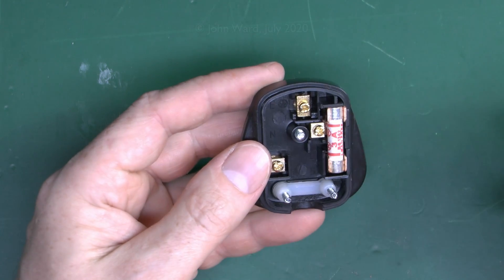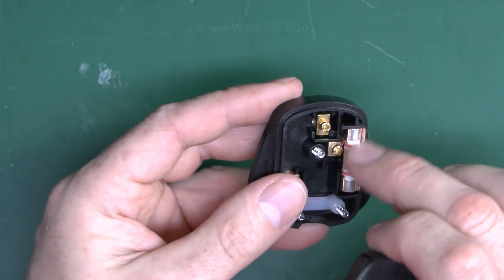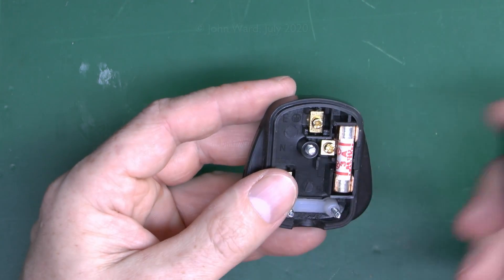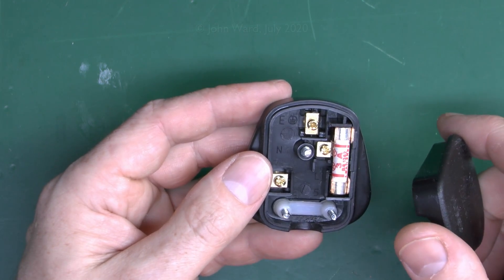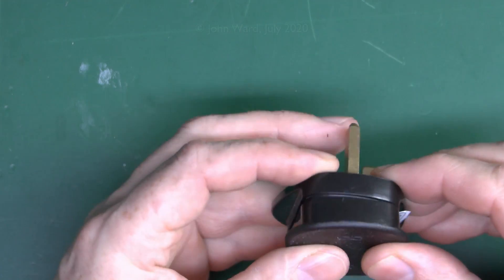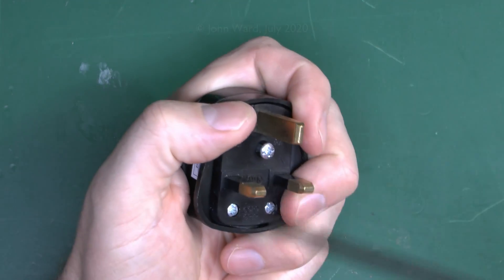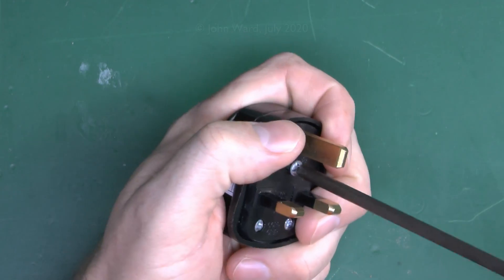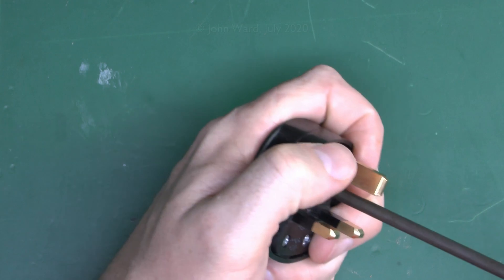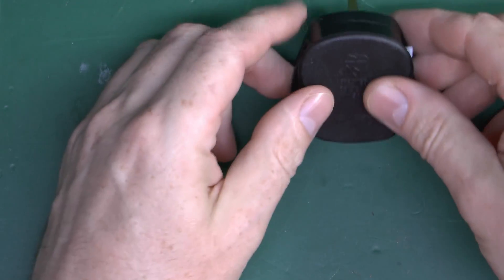Loose connection is very common there, or possibly the fuse holders have gone a bit weak, or someone's put the inappropriate fuse in there which doesn't fit properly. So warm in normal operation is certainly not a problem, but certainly getting hot, if it's hot to touch, then clearly that is not good enough.